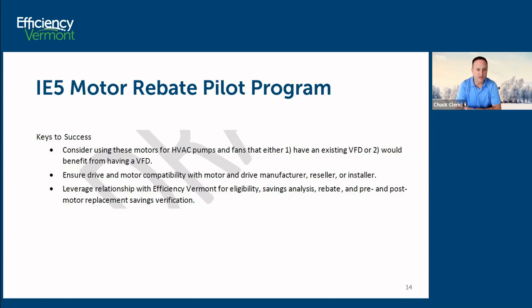Can't belabor this point enough. Ensure drive and motor compatibility with motor, drive manufacturer, reseller, installer. So there's often a variety of folks involved in the supply chain. There's of course the OEMs, there's resellers, there's contractors. Make sure you have good communication up and down that line to make sure that these new motors work with the existing drives. If you're ordering an integrated motor drive package, you don't have to worry about it, that they're pre-set at the factory and they're certainly compatible. But for existing drives, you want to take an extra moment to make sure the compatibility is there.